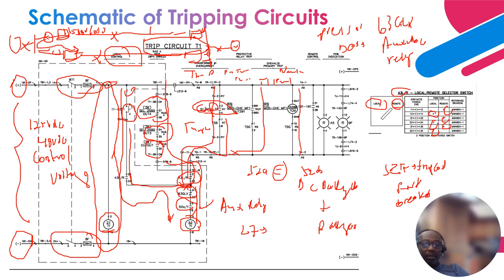So here it's a trip coil monitor, right? Very, very important, because, like I told you, very long transmission line, hundreds of kilometers, right? And very high voltage, right? And so very important that the trip coil is monitored, to make sure. Remember I told you that the coil can fail, it can burn, it can have an inadequate voltage, there are so many factors that can cause the trip coil to malfunction, right? So it is very important that you monitor the healthy status of the trip coil, and that is what this auxiliary relay does. So TCM means trip coil monitor. It monitors the trip coil.